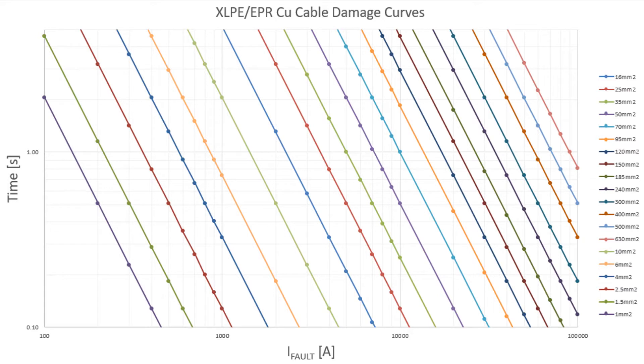Another way these damage curves are very useful is when we do our protection coordination studies to ensure that the protection device which protects the cable, that the actual trip current curve for the protection device lies below the cable damage curve with a sufficient margin of safety.